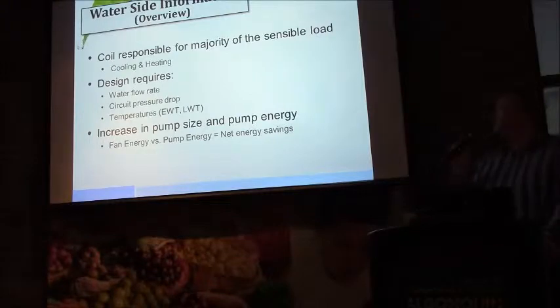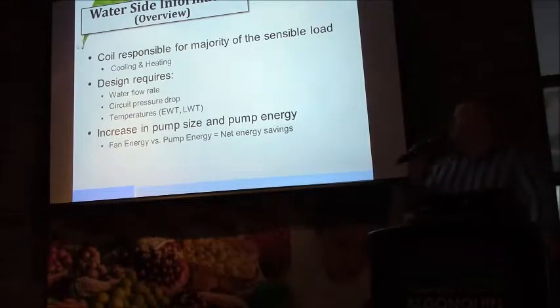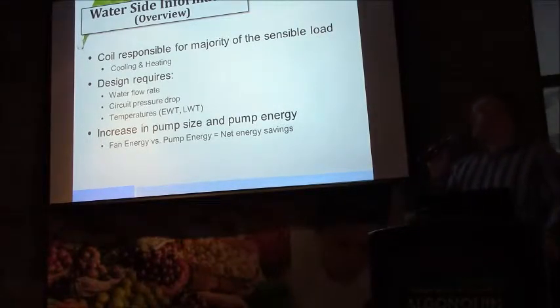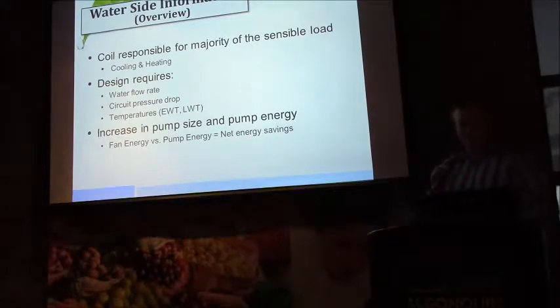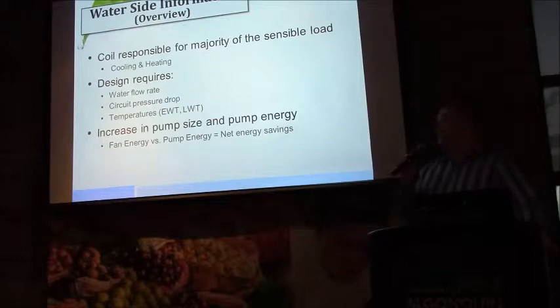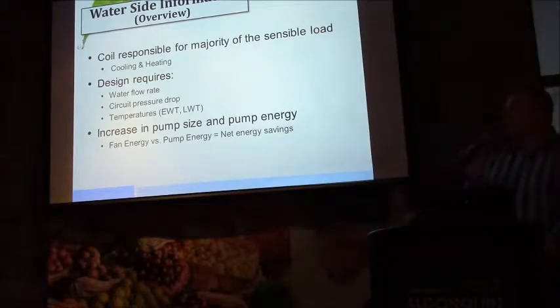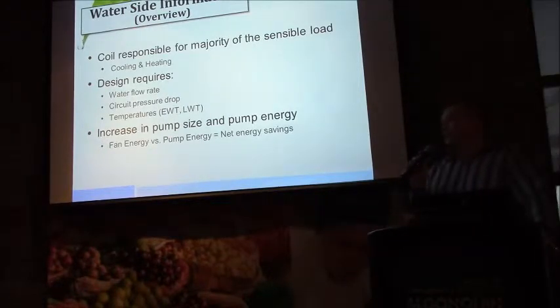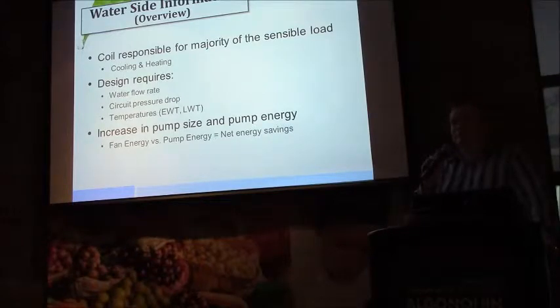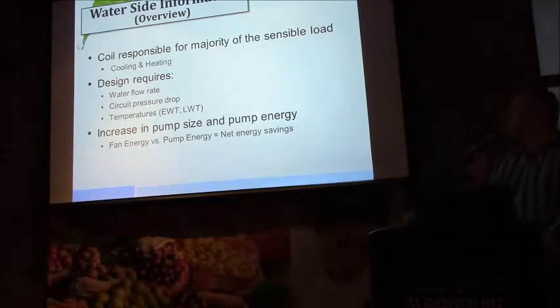So the goal is to put the bulk of the cooling onto the cooling coil, as much of it as we can. The primary air is there, obviously, to offset our latent loads and meet our min vent. We look at the water flow rates, and in general, we're driven by minimum flow rate to achieve turbulent flow, so a Reynolds number of 4,000 or so, which on a half-inch tube is about 0.65 GPM, give or take.